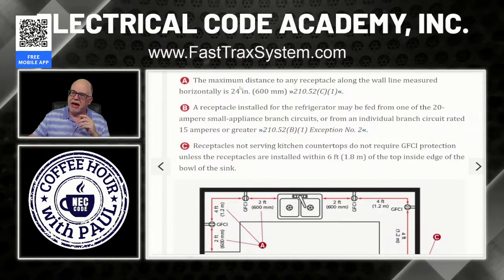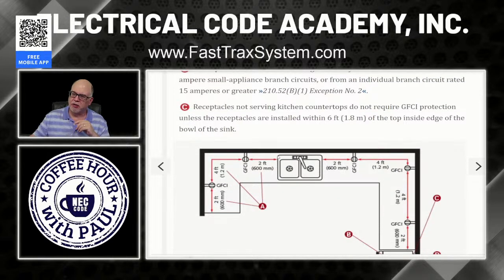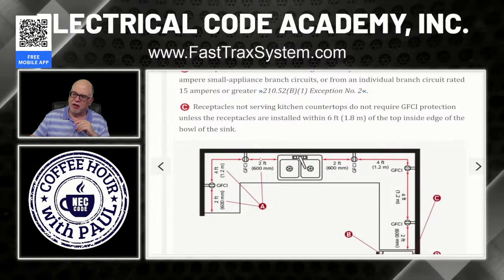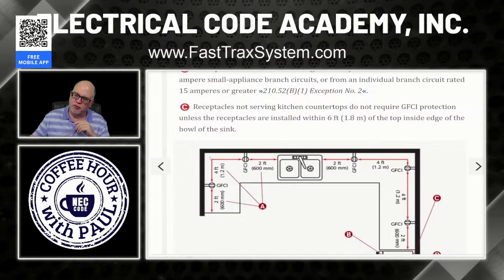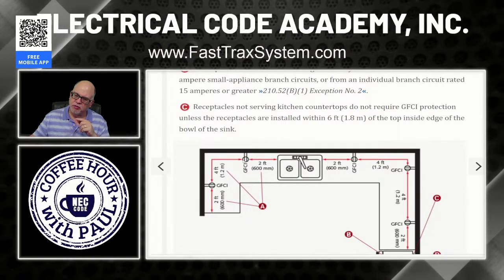A, the maximum distance to any receptacle along the wall line of the counter measured horizontally is 24 inches. So here's the break in the counter for the sink. I have to have one. I can't go more than 24 inches and have a receptacle. Then I can go up to 4 feet, because if I go right here in the middle, I'm within 2 feet of this receptacle, and I'm also within 2 feet of this receptacle. So that's the 2 foot, 4 foot rule.